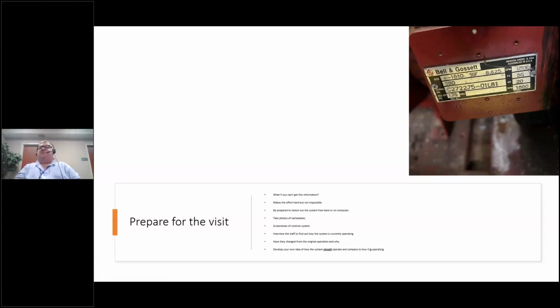What I want to get out of this - you look at that feet rating, say 55, and convert that to PSI. That's something to watch for when you get on site: are they operating at or above that number? Because it'll never accomplish that at that flow. You want to see numbers below that, showing you can work within what this pump is designed for.